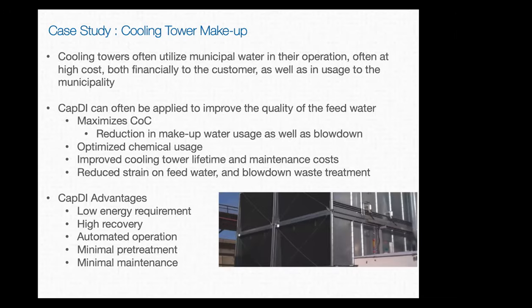Cooling towers often utilize a lot of water as well. In the way that they work, fresh water will come in, it will get evaporated, condensed. During that process, some of that water is lost, which will enable that basin to concentrate up and increase in TDS level, at which point they will need to blow that water down or get rid of that water to prevent that cooling tower from scaling up and potentially becoming corrosive and causing any issues with the cooling tower.